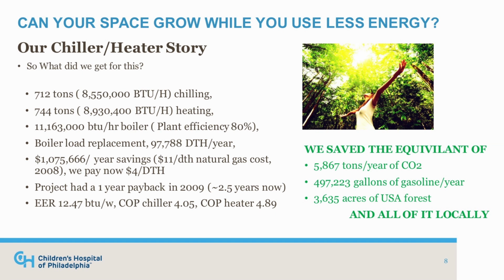It's about 712 tons of cooling and a little bit more than that of heating. It has the effect of an 11 million BTU per hour boiler at 80% efficiency. It essentially replaced almost 100,000 decatherms of boiler capacity a year.